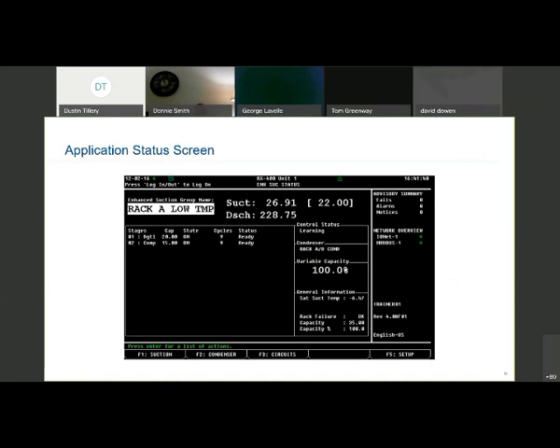All right, so the application status screen. This would be the screen that you would see if you were to go into that specific application. The example we're given here is our enhanced suction group. On this screen right here, we see things such as the name of the group or our real-time suction pressure here. What is actually at that transducer? In the parentheses, we would have our set point. What is our suction pressure set point? That would be easily seen by the technician right there.